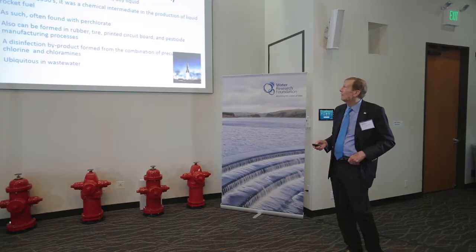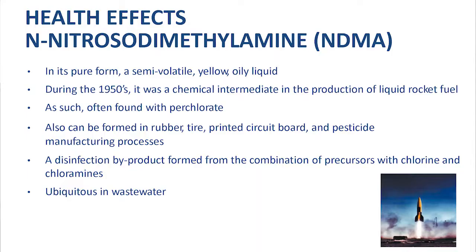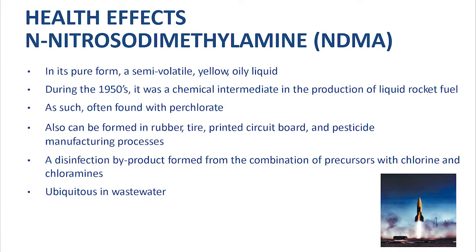One of the reasons for removing NDMA is because it's carcinogenic. There's a study going on now to see what the activated sludge plant could do to remove it at Los Angeles Sanitary District. What they find is basically most of the precursors for NDMA are removed in the activated sludge process. But the problem is they have no proper control of their scum removal, so they add polymers, and the polymers actually turned out to be the source of NDMA.